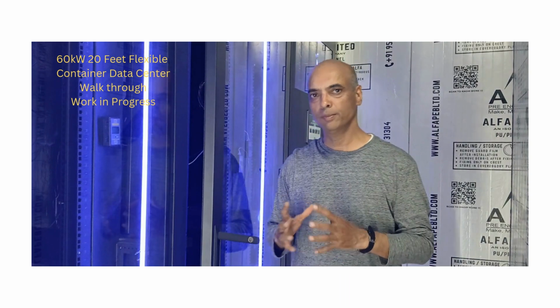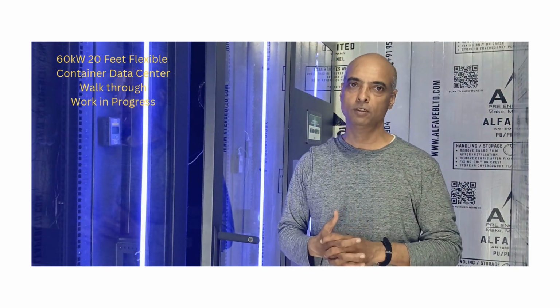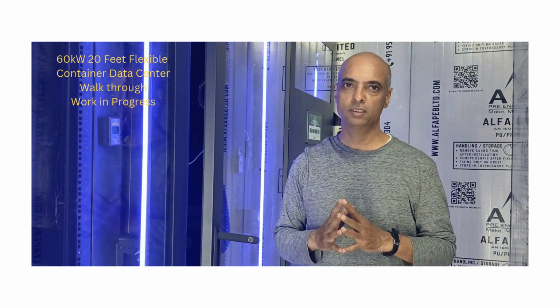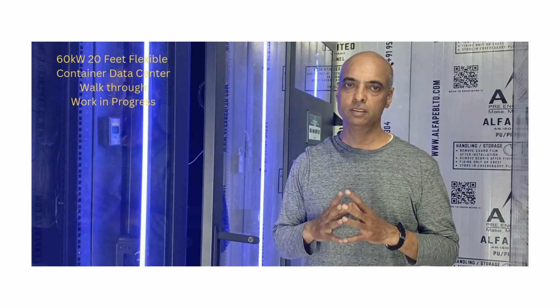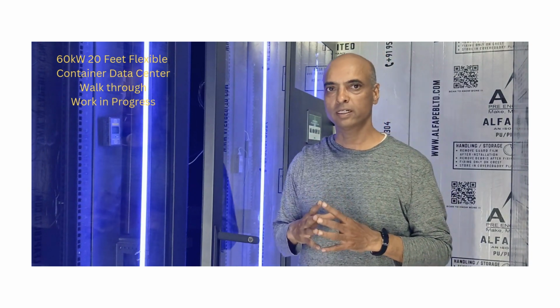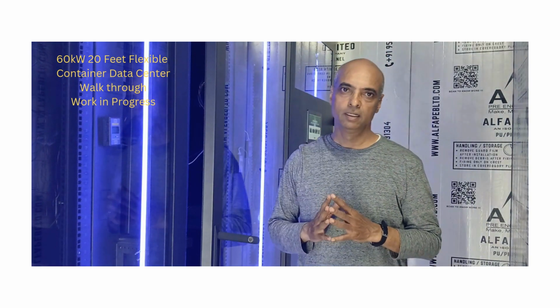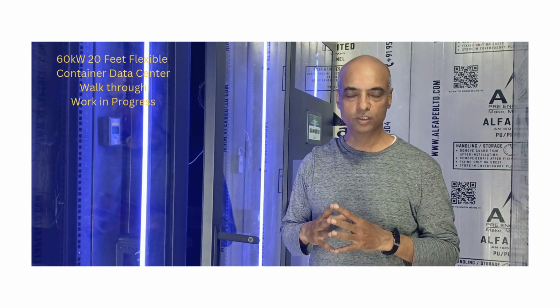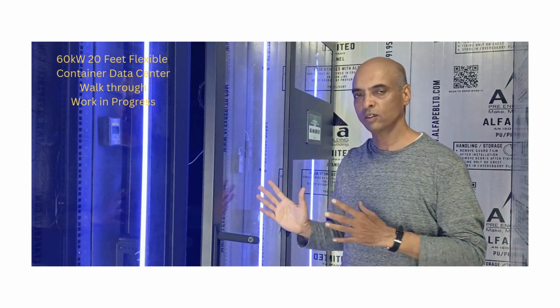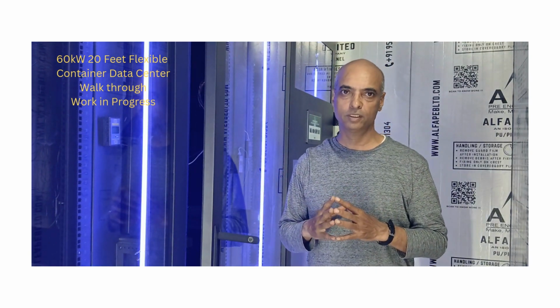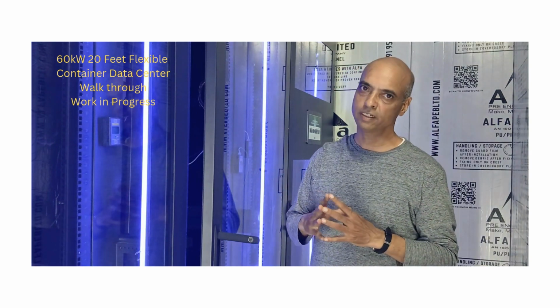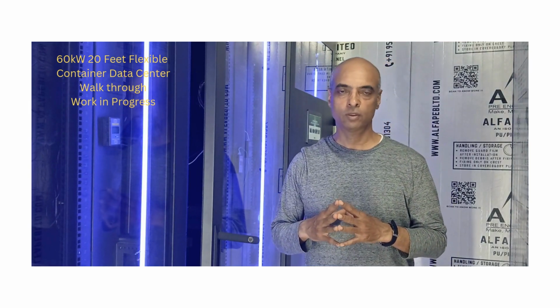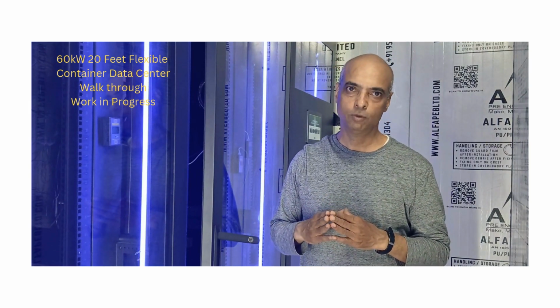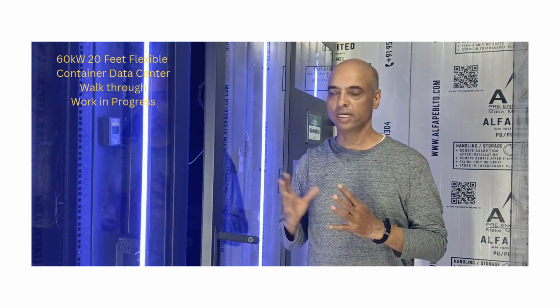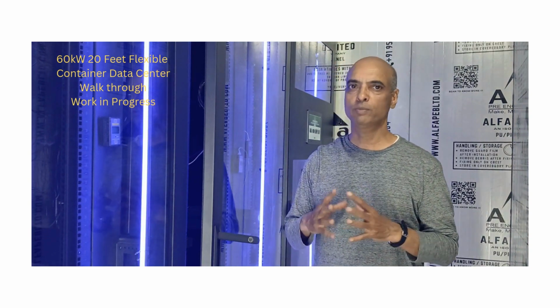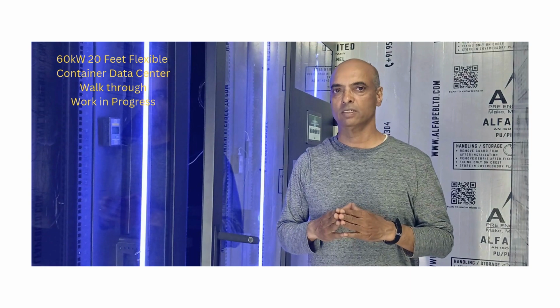I'd like to explain the EMS solution we've developed. It's a completely homegrown solution based on the Modbus protocol. This is very important for small data centers to monitor temperature, humidity, and smoke sensors. All the racks are smart and can adjust temperatures based on the heat generated by each server. This intelligence helps engineers know what's happening during peak hours, and we can develop a lot of big data analytics based on this EMS solution.